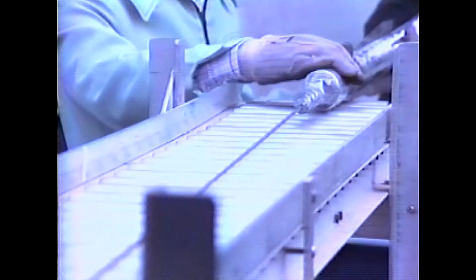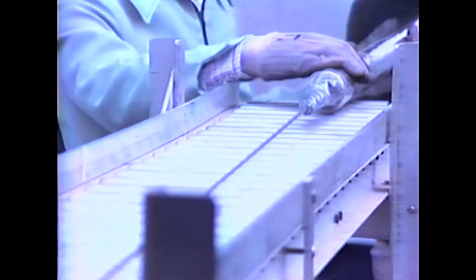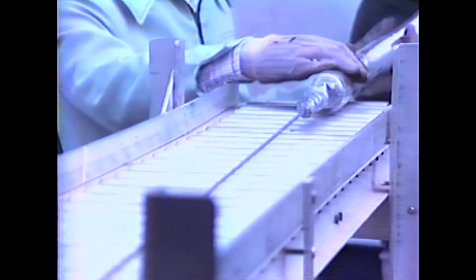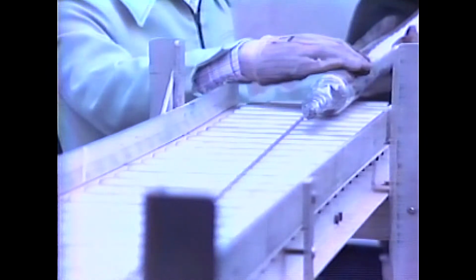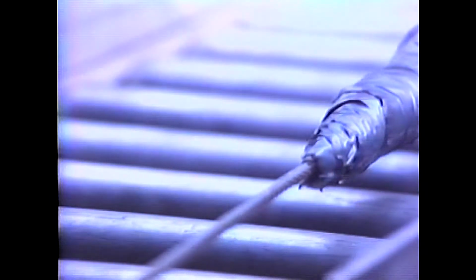With the reel in position, the cable was pulled into the enclosure pipe in 2 operations. He's got to pull it. You want that cable there to be pretty tight. First, about 400 feet was drawn into the pipe and the cable was cut. Then a second cable was drawn in, thus allowing a circuit to be made with 2 cables, each about 400 feet long, before final trimming.